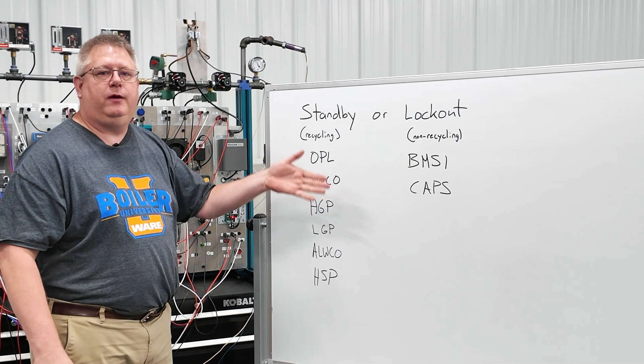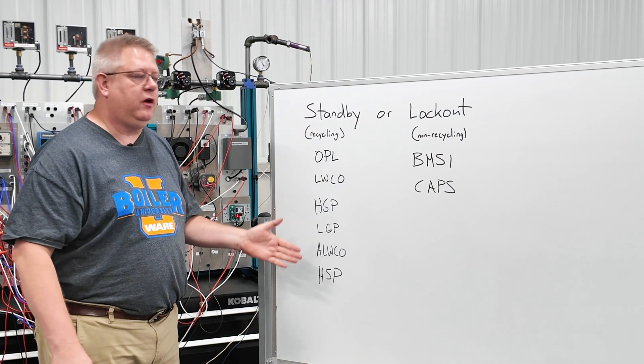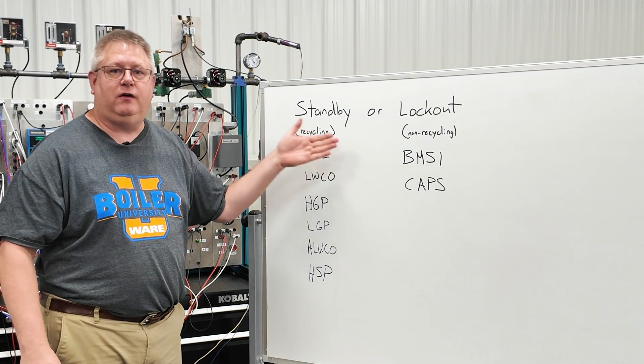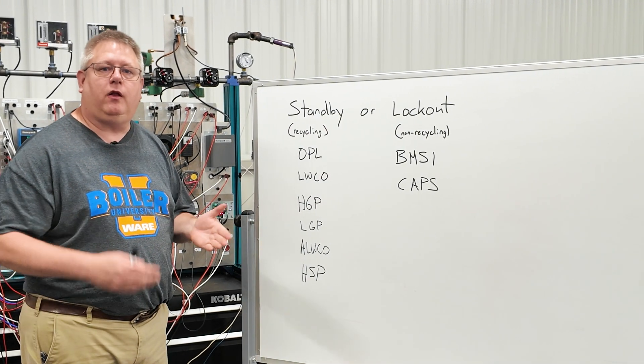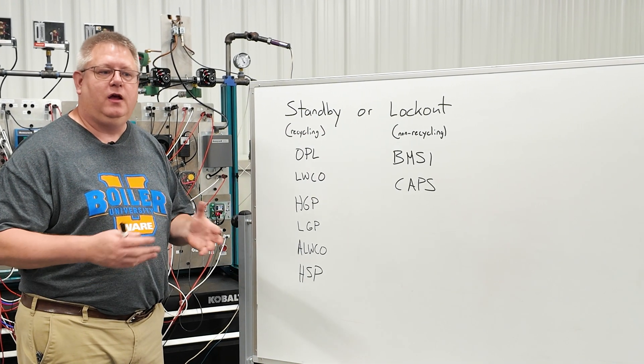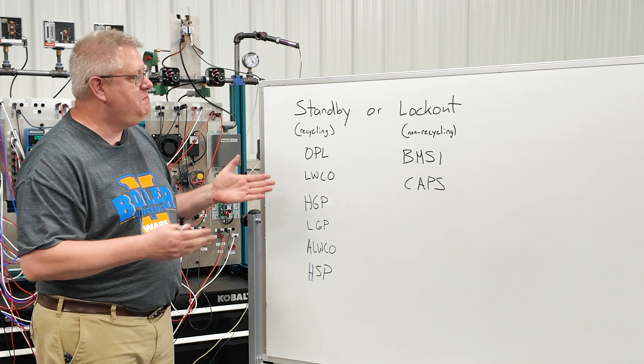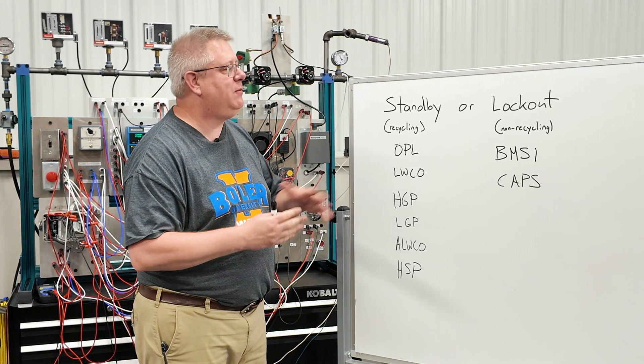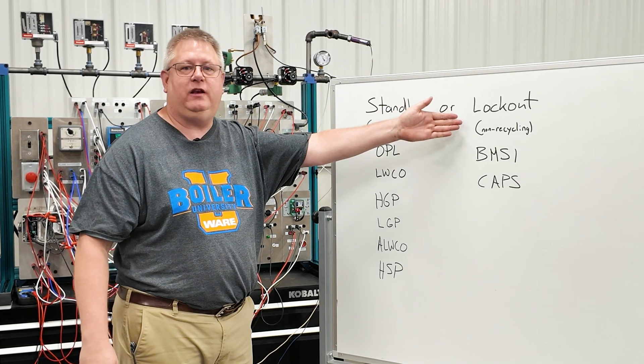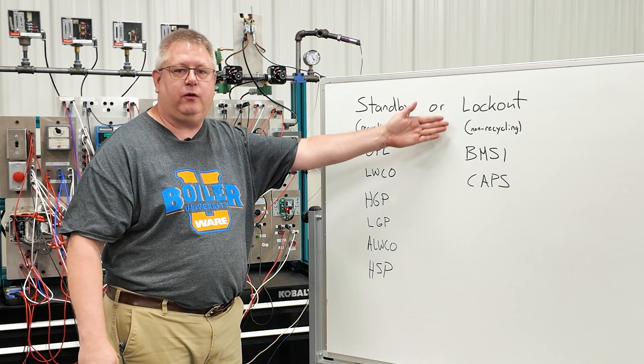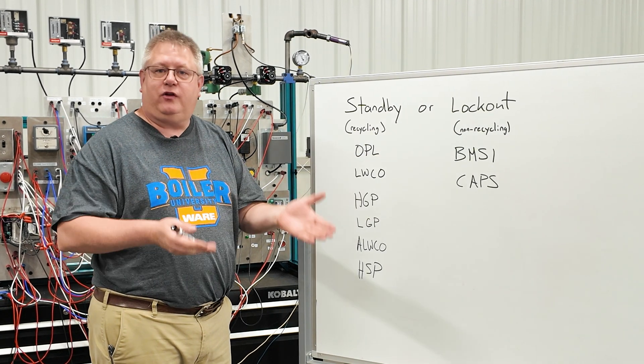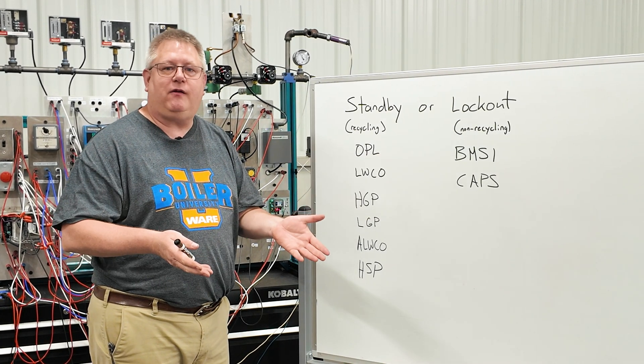Now that we've tripped all the limits on the board, we basically have a list of what switches are in each interlock circuit. We've definitely minimized what we need to check for getting a running interlock fault. Not as good as having a diagram, but better than having nothing.